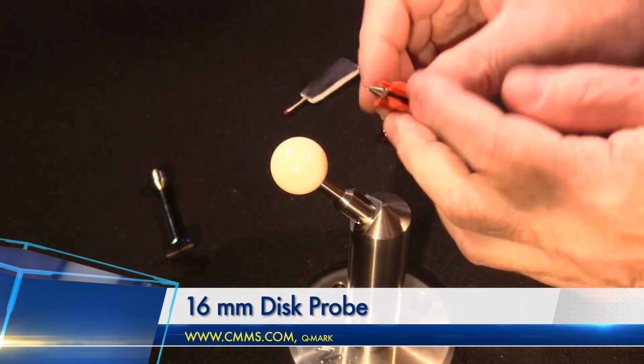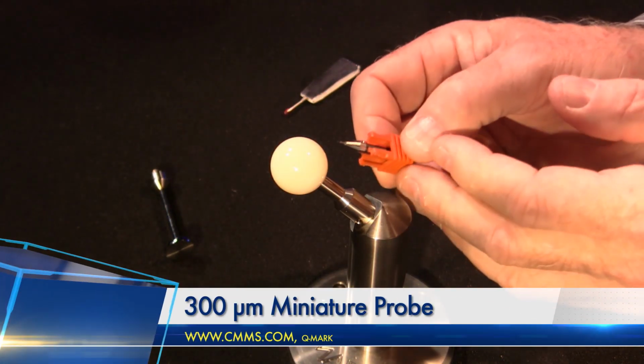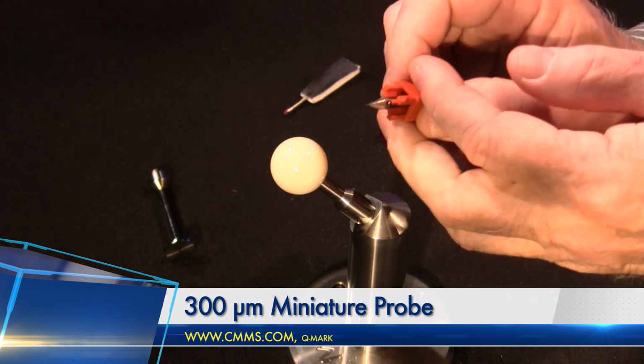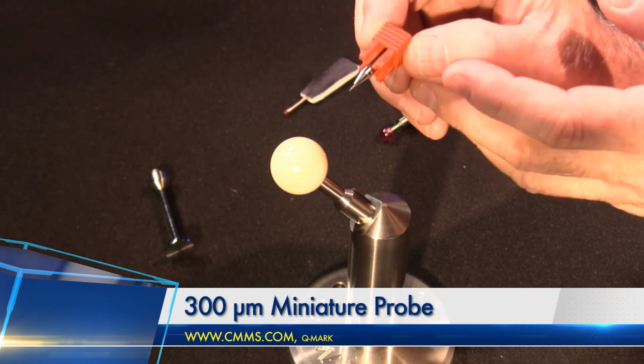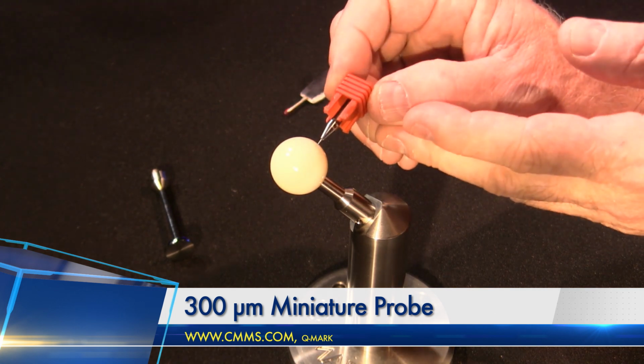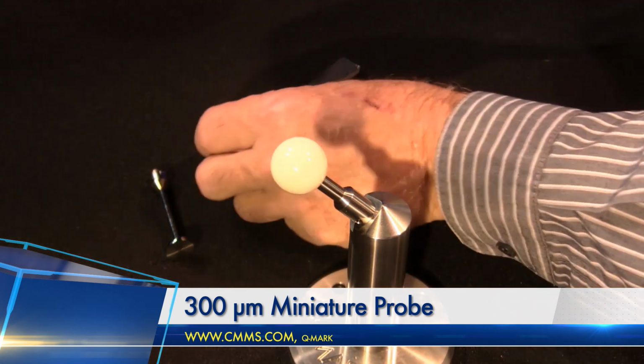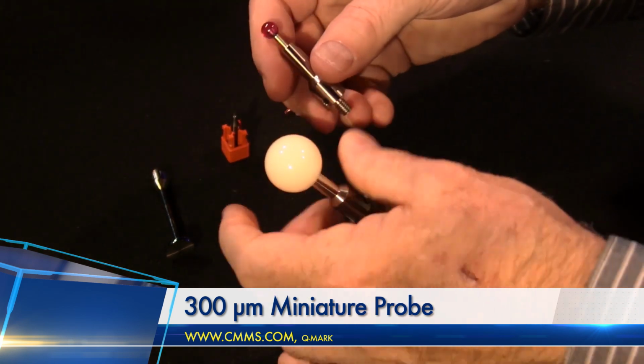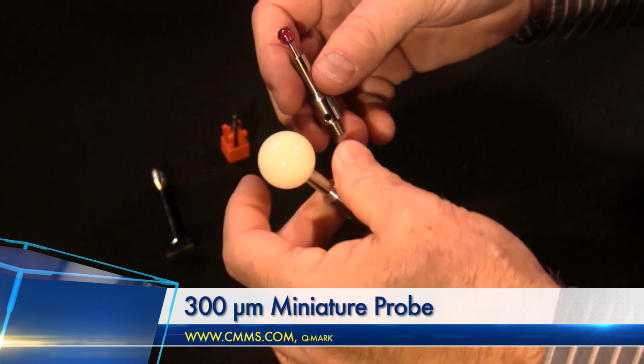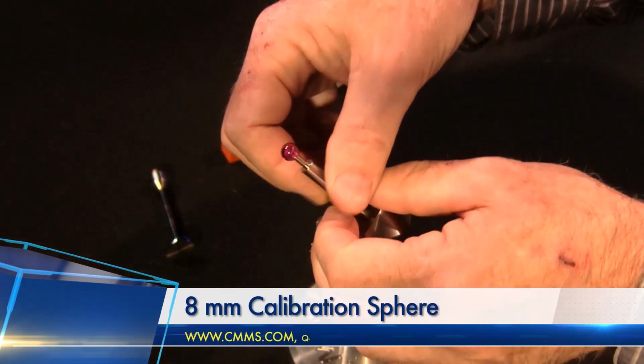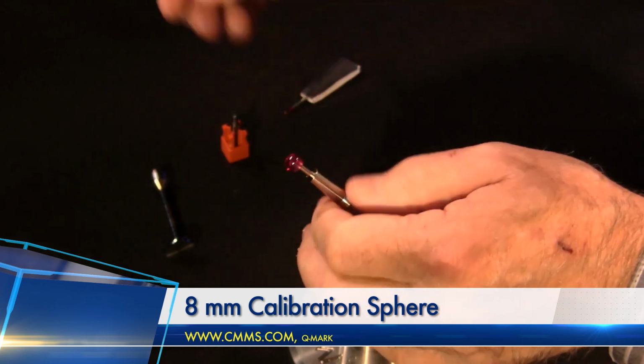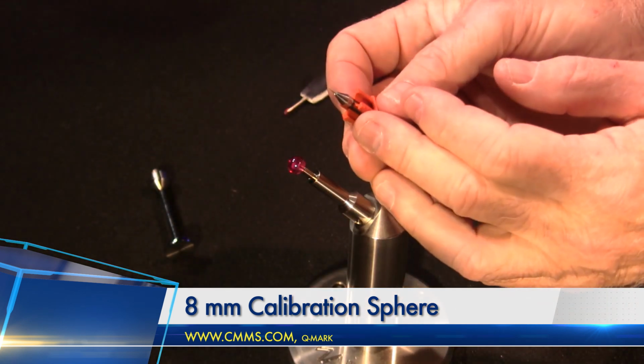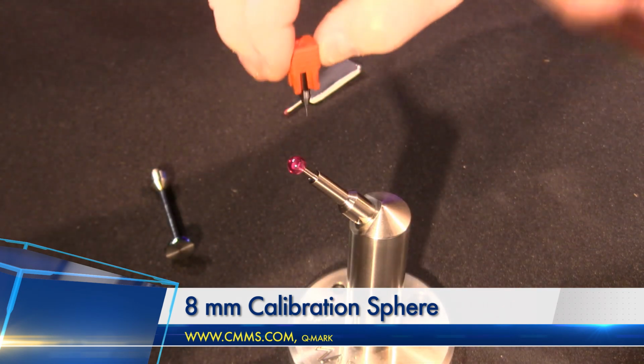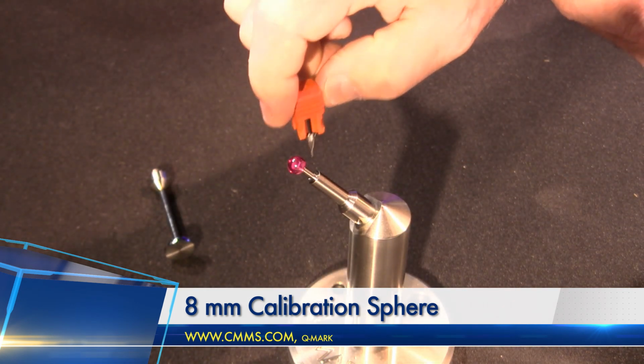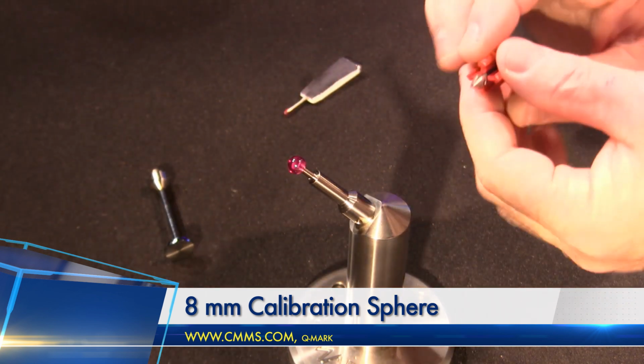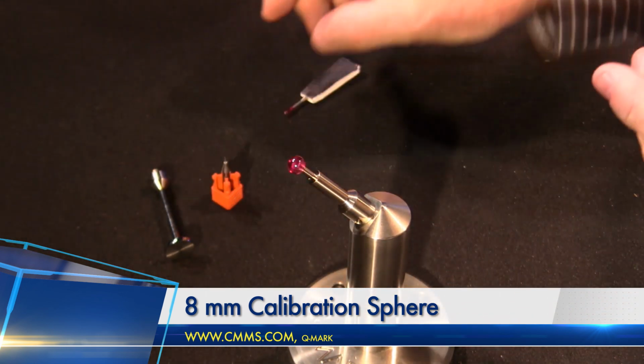Next, we're going to look at a 300 micron miniature probe. Again, this is an off-the-shelf probe from QMark. I still have it in this little holder here so that I don't have to get my fat fingers in the way. So it's 300 micron. They make these down to 100 micron. And again, we're going to use a different calibration sphere. We're going to use the 8 millimeter calibration sphere in this case, so I'm just going to swap this one out. Again, what I'm showing you today are all off-the-shelf products from QMark. So we're going to take our 300 micron miniature probe and we'll use our 8 millimeter calibration sphere. We'll take our measurements and use that data to calibrate our miniature probe.